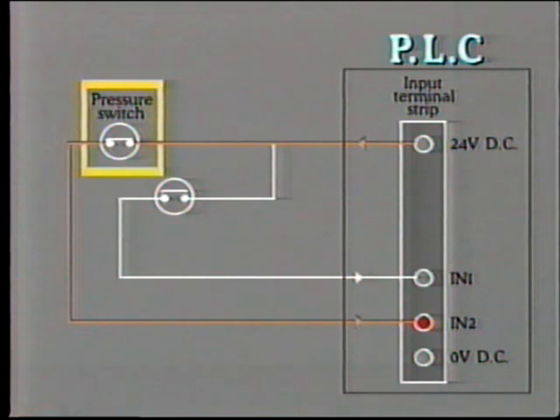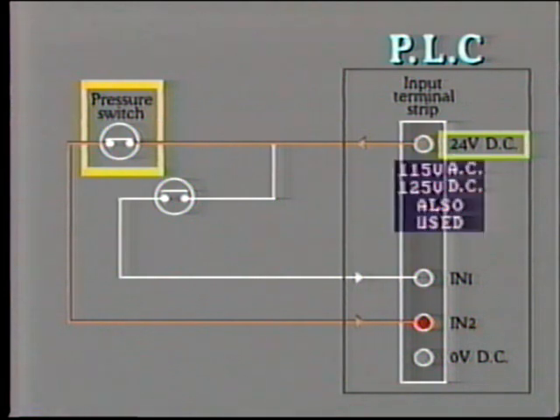Here, the voltage source is obtained from the PLC itself. The advantage of this is that it allows us to determine the level of voltage which will be applied to the circuit. Quite commonly, this is 24 volts DC, but other voltage levels such as 115 volt AC or 125 volt DC are also used. All of these voltages are far too high to be fed directly into the CPU, so a certain amount of signal conditioning is required at the interface.